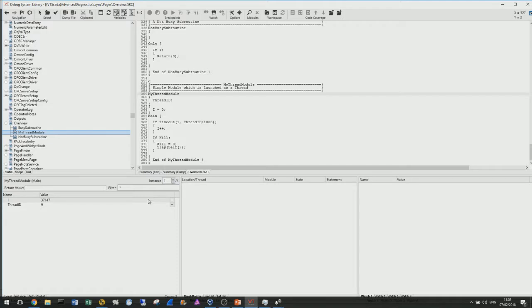Nothing's live or updating because it's running from the dump file. But you can see the value, for example, of I at that particular time. So if you take it from a live SCADA system, you're able to actually go in and see the value of the variables of the data acquisition on any of the pages. You can see the state of any drivers, any communication statistics. Internally, we can see lots of information. So it's a really very, very useful diagnostic tool, all based on the premise that you need to actually be able to take the dump file.